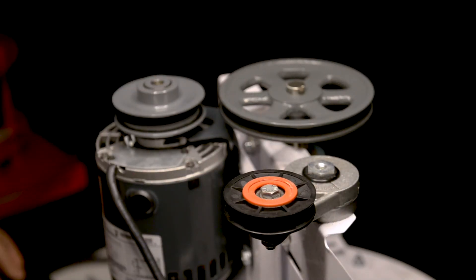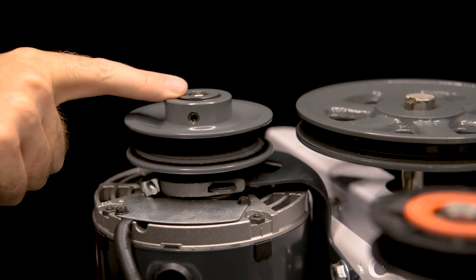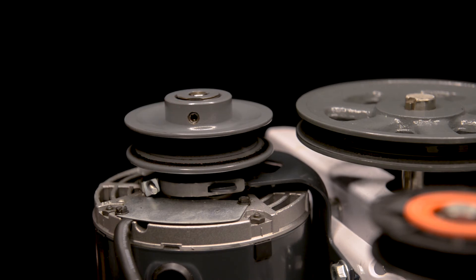Most fans provided with motors of less than five horsepower should be specified or ordered with a variable speed or variable pitch drive set. The pulley mounted on the motor, sometimes referred to as the drive sheave, is adjustable and provides an adjustment range of approximately 20 percent or more without needing to replace the pulley.